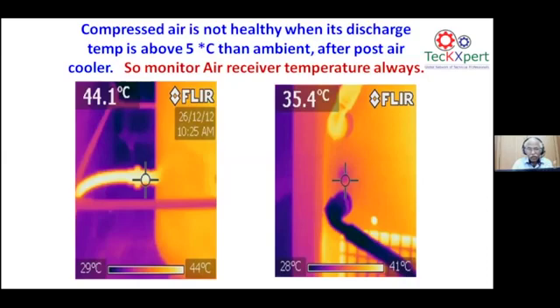Not only on the dryer, if you see the air receiver, the ambient temperature is around 35, but the air receiver temperature is showing 44. It means the post air cooler is not working. The compressor is pumping hotter air outside, so automatically the CFM goes down. When there is cool dry air at the inlet, you will get at least dry air at the outlet. If the air is coming very hot at the inlet, the air at the outlet will be much hotter.